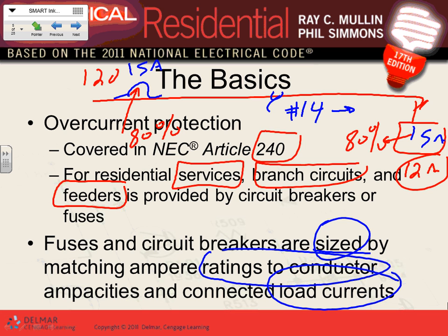We fully understand our protection device protects the conductor and the equipment load. Cool? And that's how the formula is. This guy cannot be more than the conductor can handle, and cannot be more than the load can handle too. Or I can't pull more load than what the circuit breaker can provide you. Otherwise, it's going to trip.